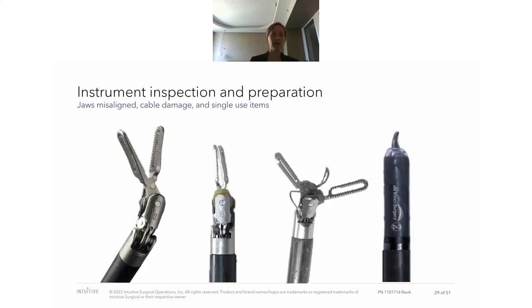And going into a bit more detail for the inspection, here you can see some examples to look out for. One is, are there still any accessories on it? For example, here you can see the sheath still on the MCS. If you do see that, obviously it has to be removed because the cleaning cannot be done appropriately if it is still on. Then also if you see cables that are loose or broken, or misaligned jaws, those instruments should be sent back and not be reused anymore. For the MCS with the sheath, it just has to be cleaned, obviously, and then it can be used.